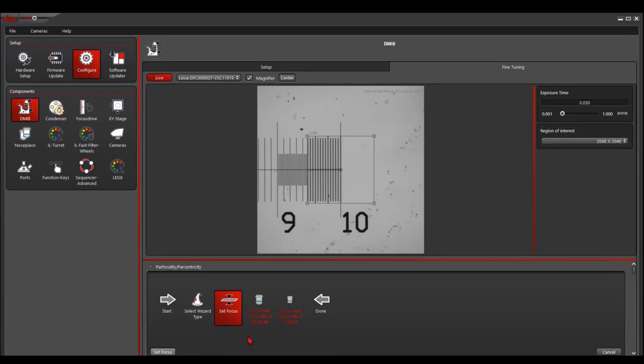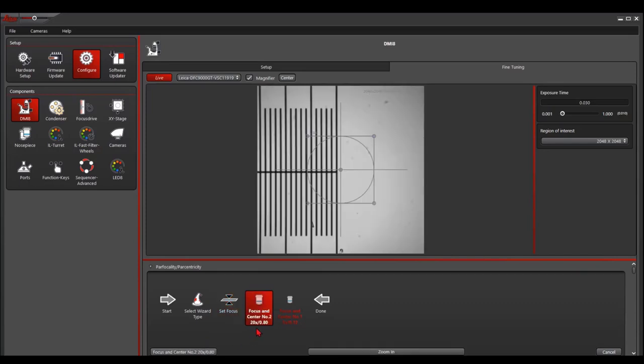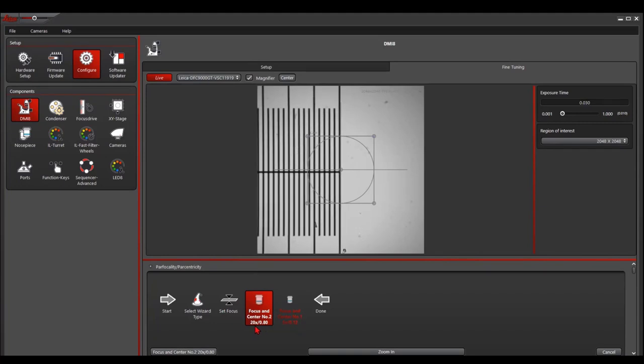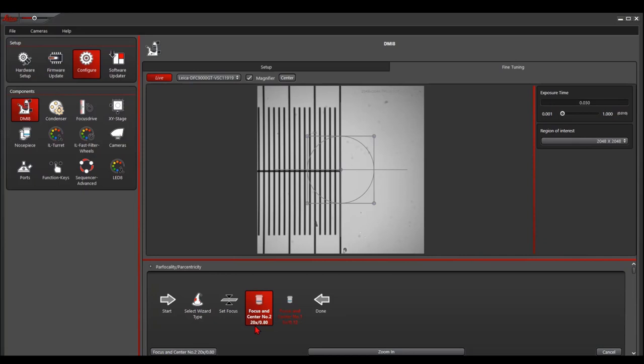It will go to the first dry lens, usually from the higher to lower. Then you move the stage, X and Y, to find the center of the object. In this case, I use the cross section of the stage micrometer.